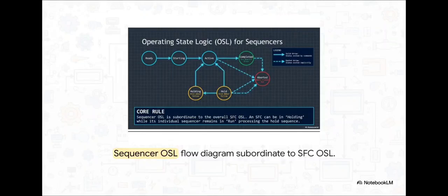Sequencer OSL is entirely subordinate to the overall SFC OSL. So this means an entire chart could technically be in a holding state while its individual holding sequencer is actually in run mode, meaning it's actively processing the specific safety steps required during that hold.